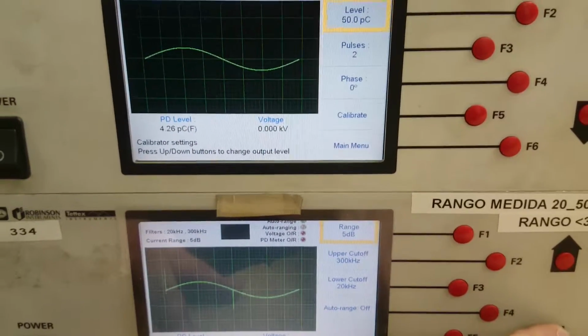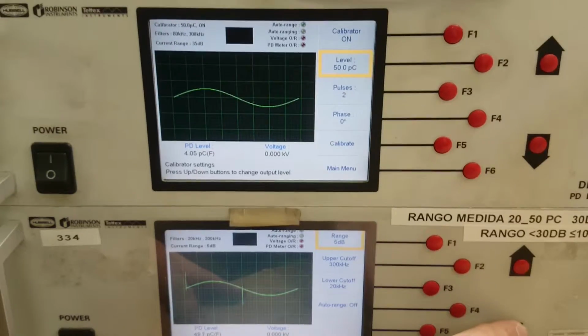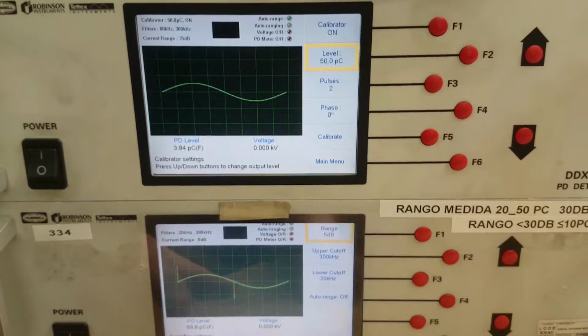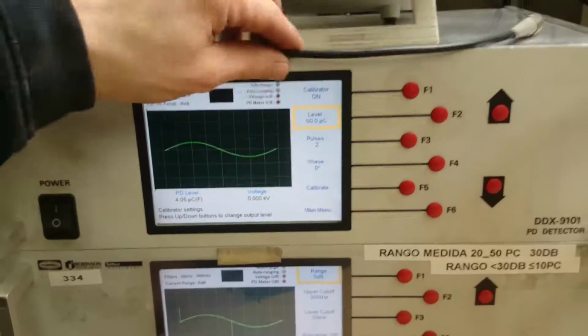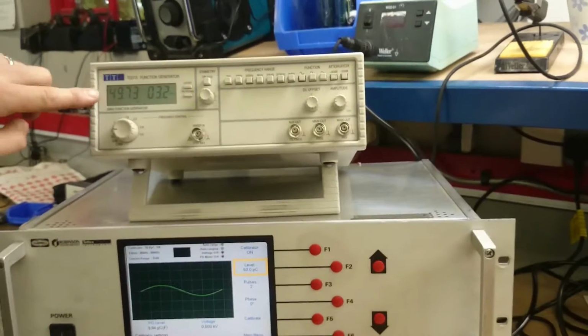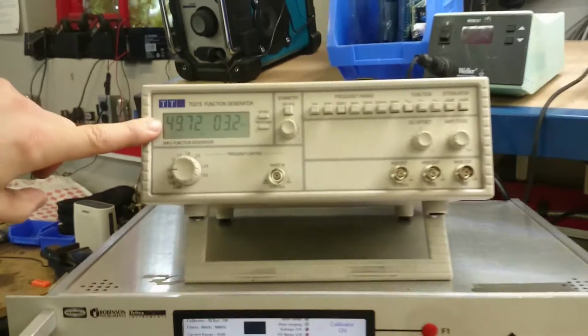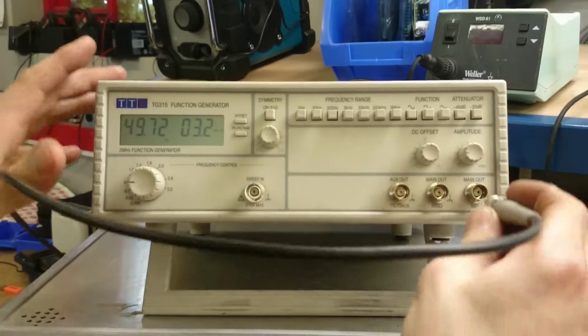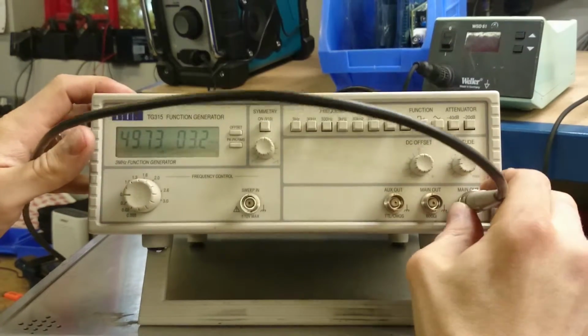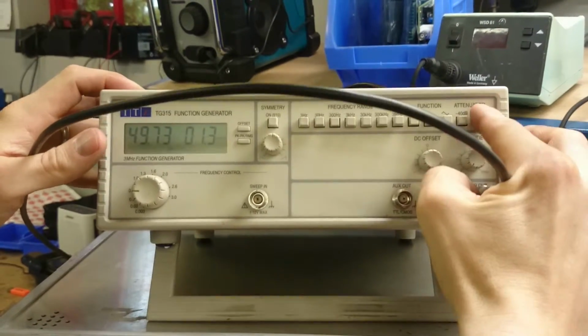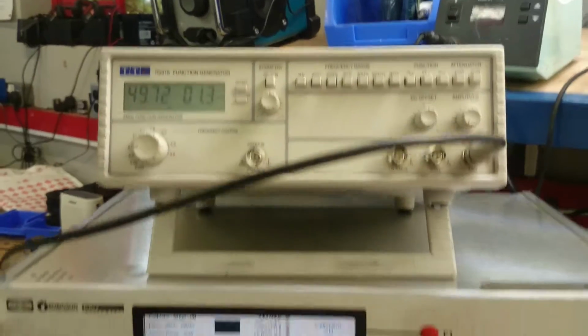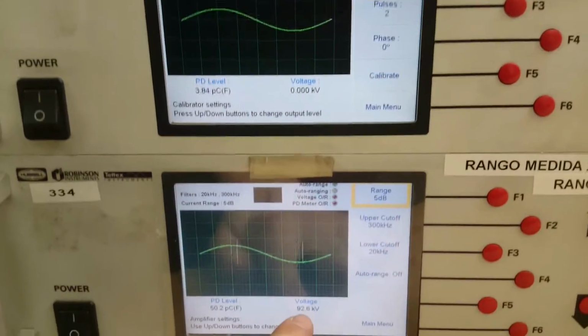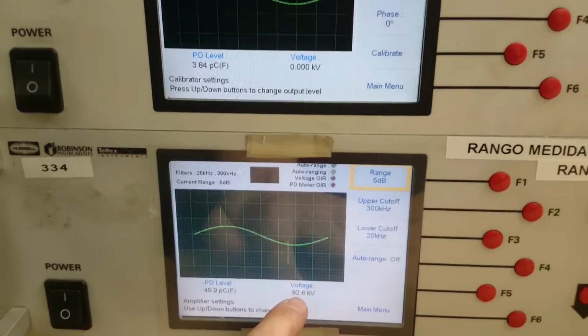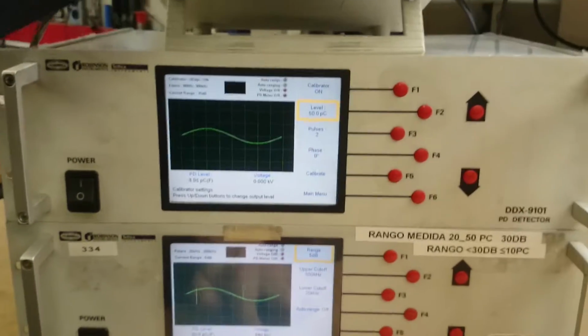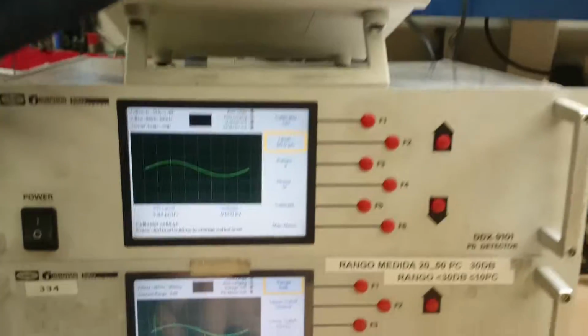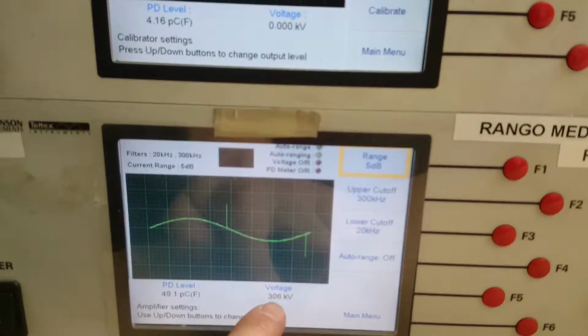And the other fault that was reported was it's not synchronizing properly to the input frequency. So this is a signal generator set to close enough to 50 Hz, and this is going to be fed into the kilovolt meter. So as I switch that on, you can see we start to get some voltage there. Got 90 kV, I'll just increase that. Thankfully it's not really 90 kV. 300 kV, getting nice and big.